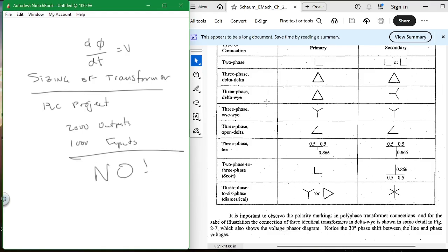No. What do you do? You actually have to look at the rating of the devices - what is the current input or output of those devices - and then multiply it by that number. In other words, if you have an output, a solenoid, that has a runtime current of 0.2 amps, you multiply that times that.